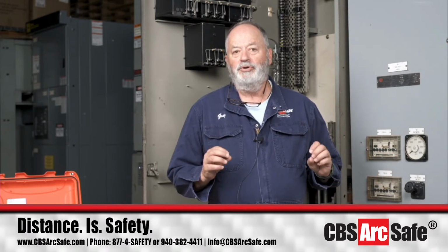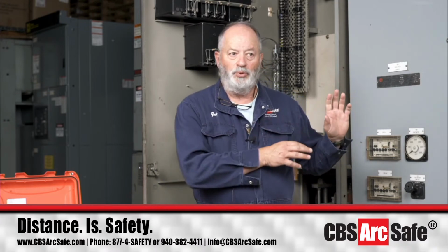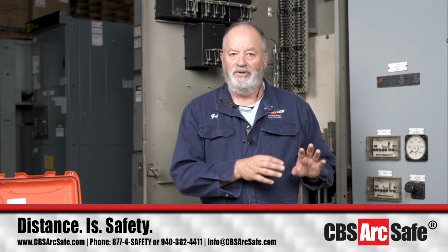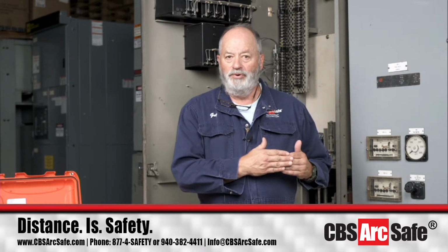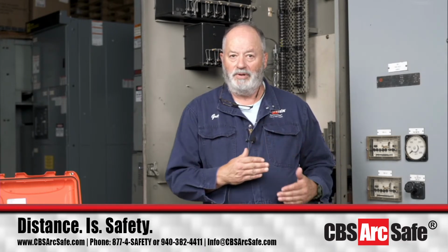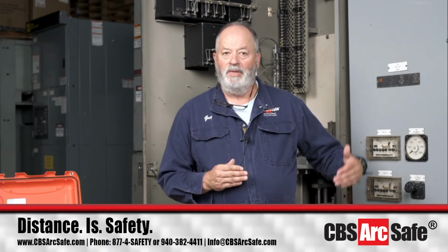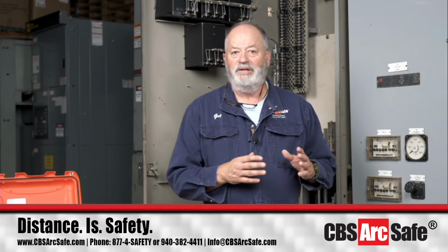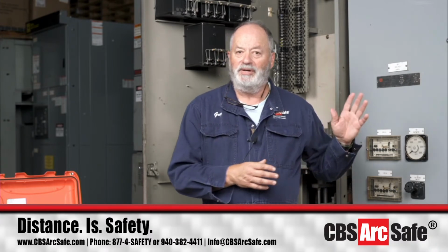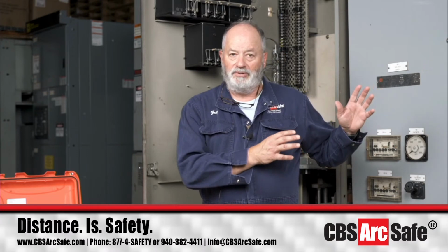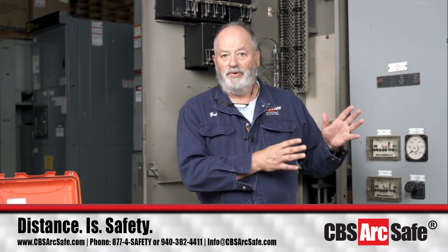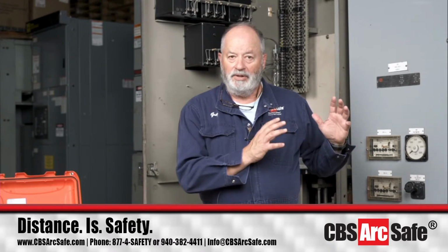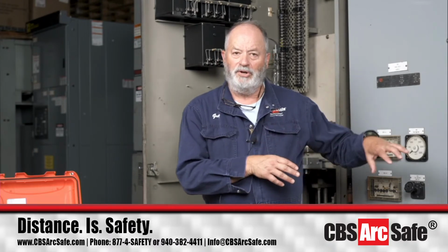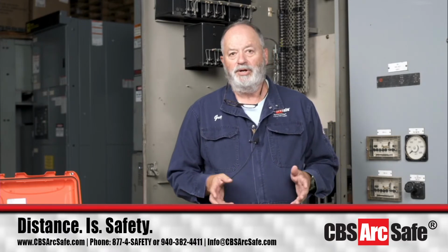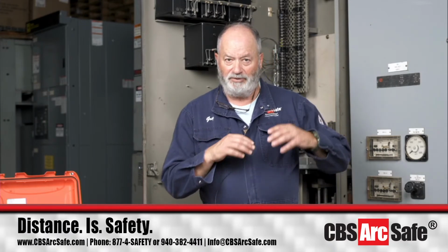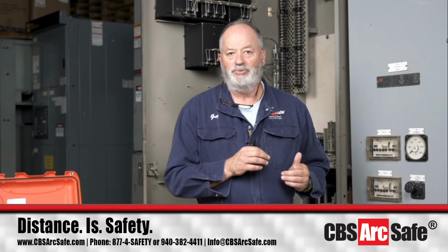The other thing that you need to know when you're doing retrofits is this: even though it says M26, M36 cubicles and stuff, General Electric at times moved the grounding plates in the back where the breaker would go back and engage to ground it, and so not all those are in the same place. So when I say contact Circuit Breaker Sales in Gainesville or Circuit Breaker Sales in New England to make sure that you've got the right equipment going in for a retrofit or even other stuff, they will check to make sure that those grounding plates that are going to engage in the back are in the right place, and your breaker is going to be compatible with your specific version of M26, M36 switchgear.